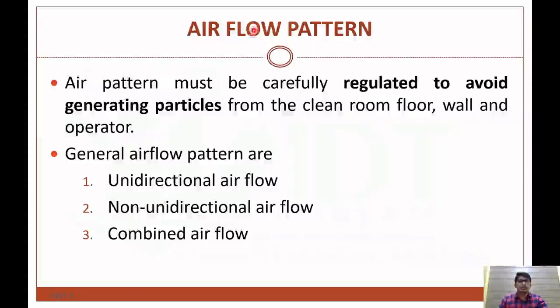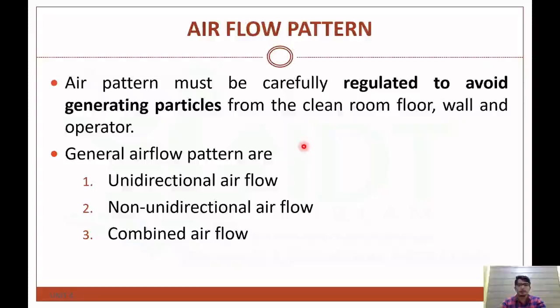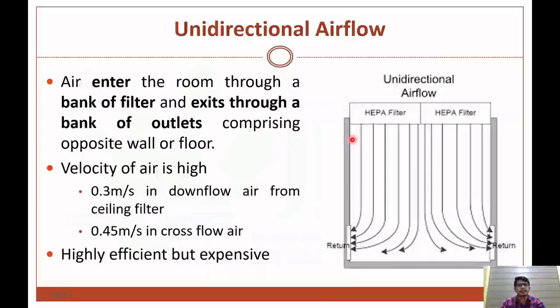Now let's discuss the air flow pattern in the laminar air flow unit. Air patterns must be carefully regulated to avoid generating particles from the clean room floor, walls, and equipment. Generally, air flow patterns are of three types: unidirectional air flow, non-unidirectional air flow, and combined air flow. In unidirectional air flow, air enters the room through a bank of filters and exits through a bank of outlets comprising the opposite wall or the floor.